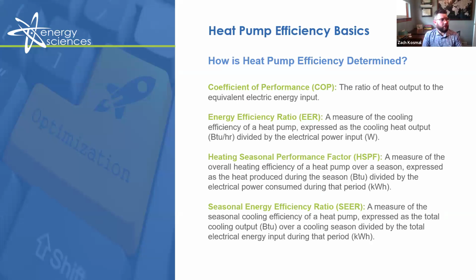So how is heat pump efficiency determined? There's several metrics. These are the four main metrics here. The first is the coefficient of performance, or COP. This is the ratio of heat pump heat output to the equivalent electric energy input. So the coefficient of performance is a unitless value. Therefore, a unit conversion is typically required to calculate this value. A higher COP implies that the unit has a higher efficiency.